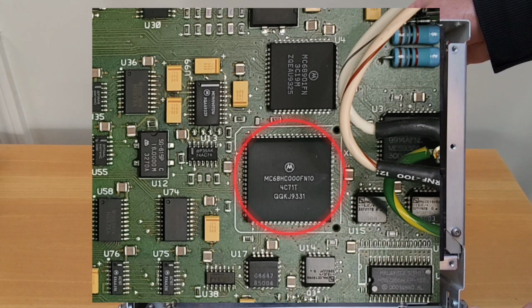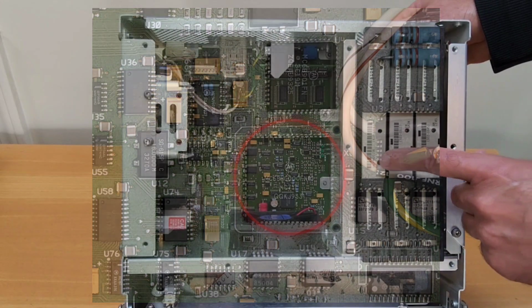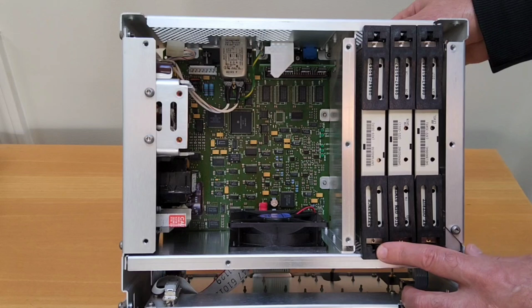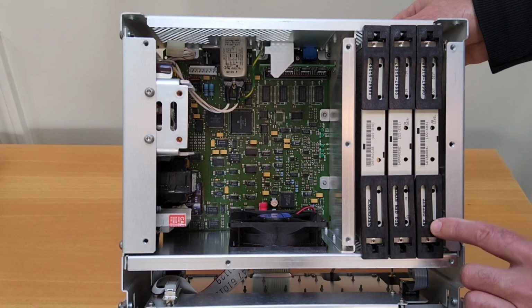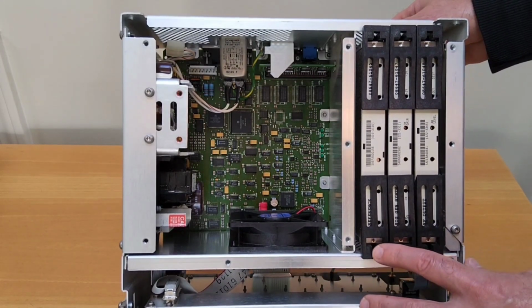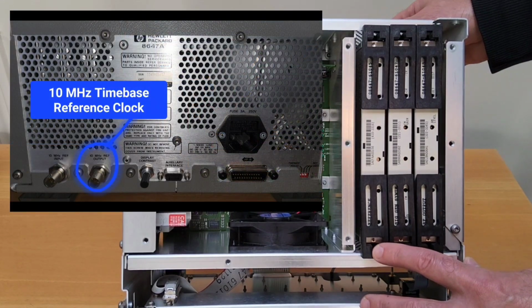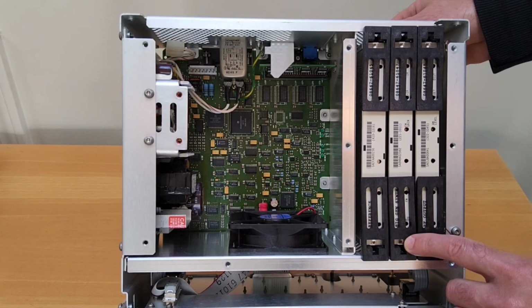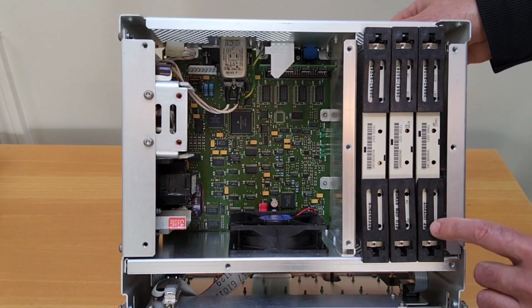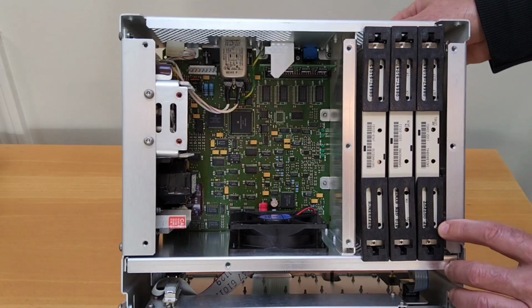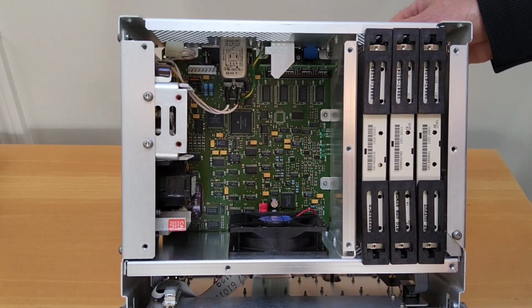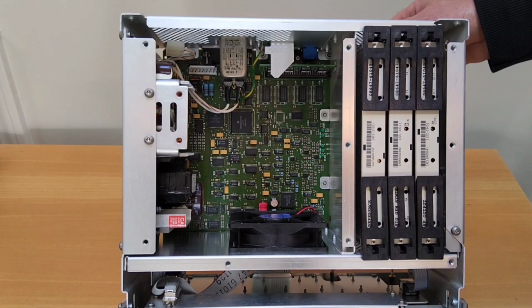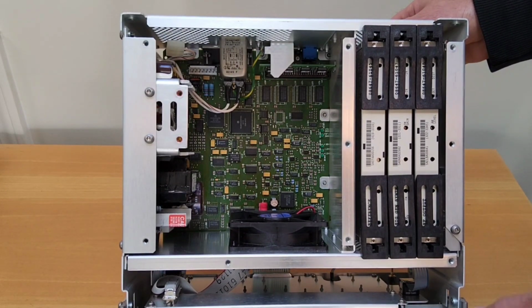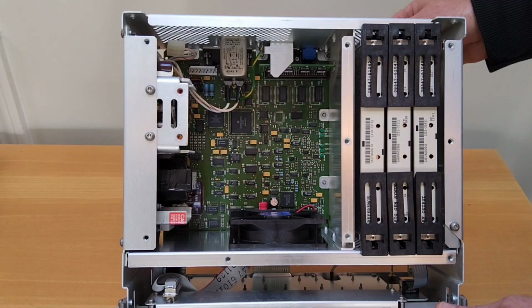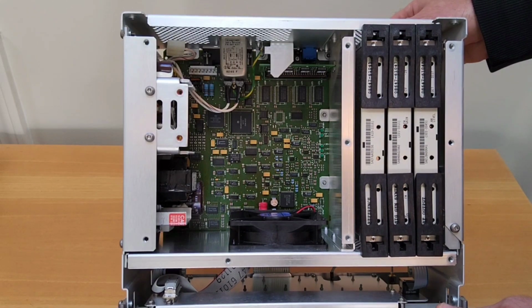These units come by default with 3 assembly kits installed. The reference kit, the synthesizer kit, and the RF output. The reference kit is where the actual 10 megahertz reference signal is generated, and the synthesizer kit is where the signal is converted to analog, and the RF is the final output. One thing that I've read quite a bit about on different blogs about this unit is that the power supply, which is a switching power supply, has issues specifically with one capacitor.